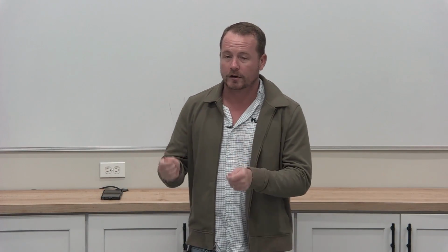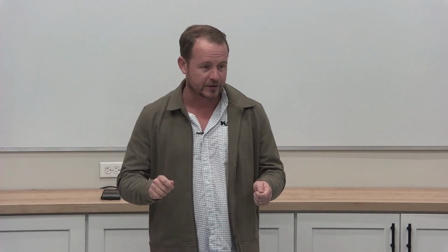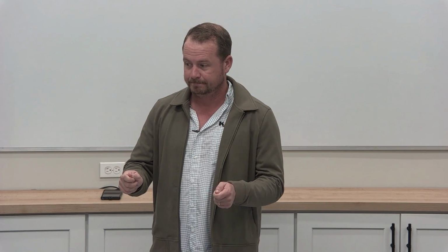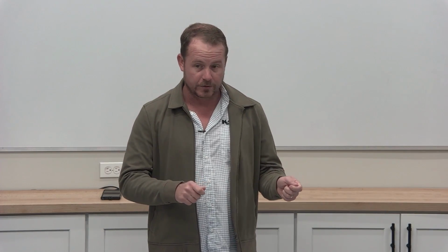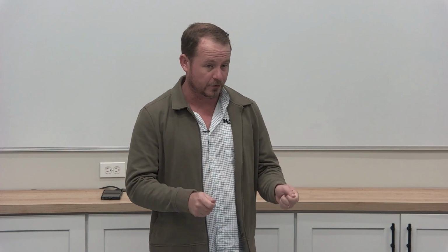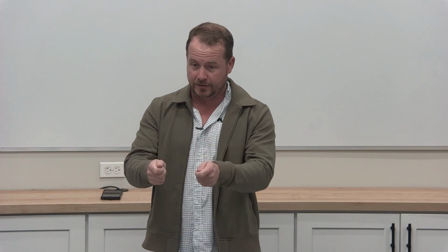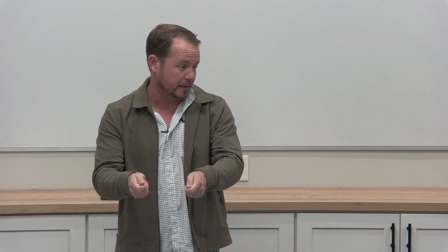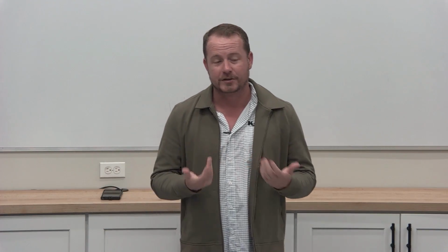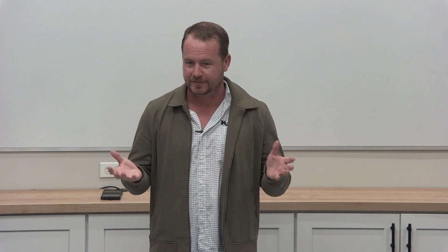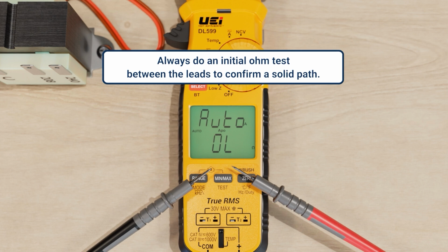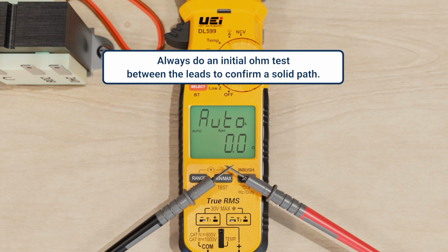Anytime you are going to use a meter for a safety test, first thing you do is what? Check across. First thing you do is you confirm that it's working in the first place. So you either check it using the voltage scale on a known power supply, or what I generally do, which is imperfect but the next best thing, put it in an ohm scale and just ring it out. Make sure that you've got a path. And then switch it to volts, and then go leg to ground, leg to ground.